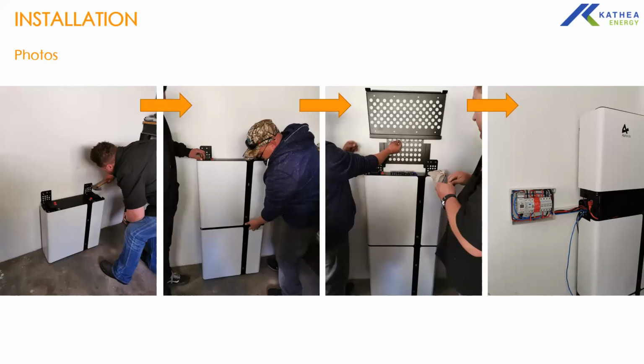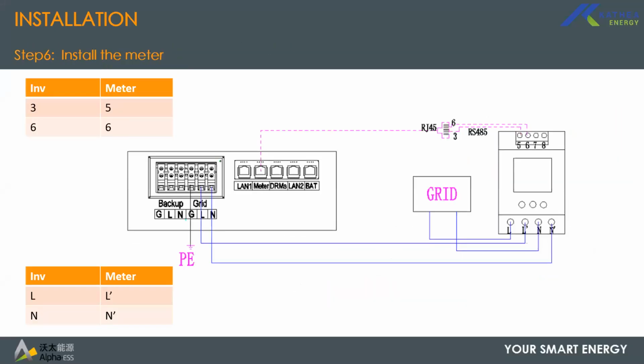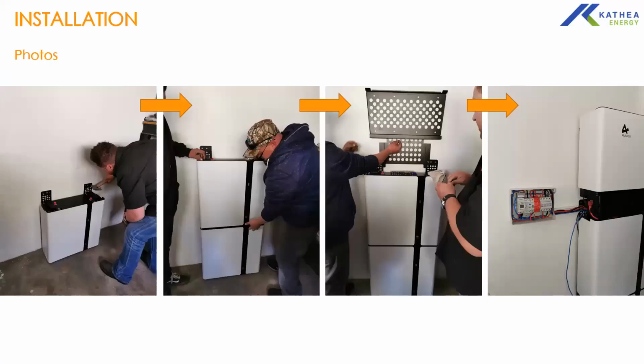Now on the battery cables, it's a parallel mode battery, so your positive is connected to positive, your negative is connected to negative. It has 2 connection ports, one pair at the top, which is the positive and the negative, and then one on the sides, positive on the left and the negative on the right. Those points are the same. So from the top battery to your inverter, you connect your power cables from the top of the battery to the left side of the inverter.